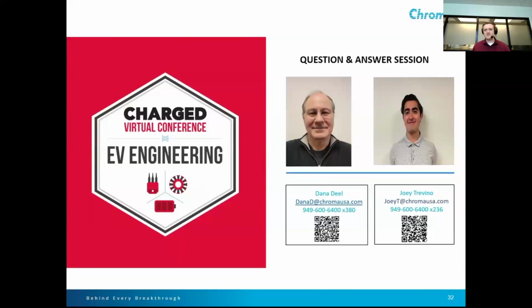Next question we have, do you need a heat sink to capture or store heat and reuse? The answer is no. The units will automatically regenerate the power back to the grid. When they receive the power, they'll automatically translate it from either AC to DC, back to AC, or from DC to AC, and it will go straight to the grid and directly redistribute to any present loads that may require the power.